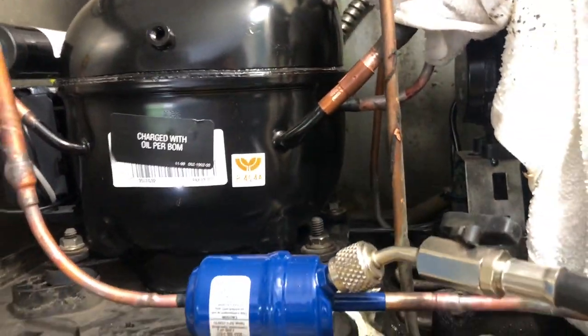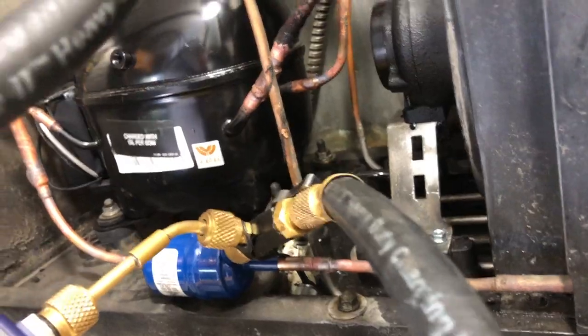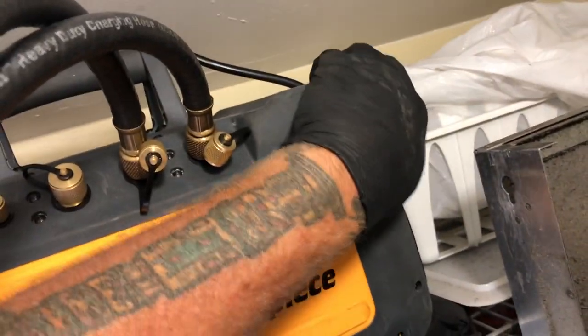I gotta raise this up after showing you the tip of the day. I'm purging the nitrogen — the YouTube police are gonna get me! I'm using the two 3/8-by-quarter-inch Yellow Jacket vacuum hoses — quarter inch fitting on one end, 3/8 fitting on the other. I got the valve core tools on; the Schrader cores are out. Using the Fieldpiece vacuum pump — let's rock it.